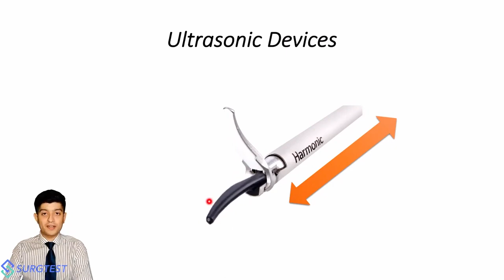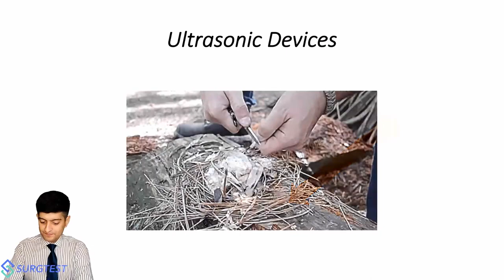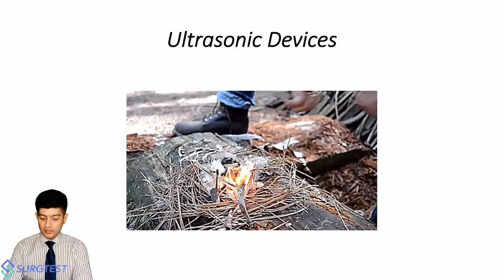This lower jaw is the one where ultrasonic energy is delivered, and it is always in line with the shaft of the instrument because it is at the probe end or the handpiece end that the energy delivery is changed. And this is the direction of the oscillation that occurs. It is to and fro in line of the long axis of the instrument. Now, obviously, because there is to and fro oscillatory movement, there's going to be friction, and that friction is eventually going to be producing heat.